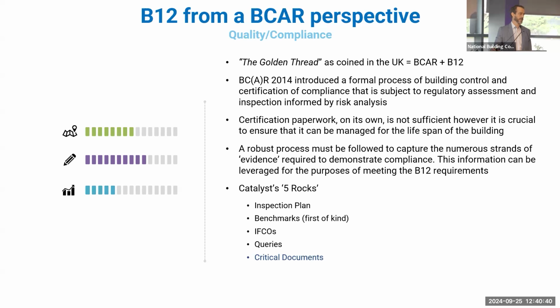Is the lifespan of that building 50 years? Is it 30 years? How long will the sprinkler system last in its current format? Does the pipework need to be replaced after a 30-year or 50-year period? All that information should be included in what's passed through from a B12 perspective. We've done upgrades of projects where you've gone in and looked at the likes of the sprinkler system and it's falling apart, to be honest. You'd wonder would it have operated as intended if it was actually in a fire scenario in basement car parks or high-rise buildings - it does make you ask the question. Anyhow, a robust process needs to be followed to capture the numerous strands and the evidence required to demonstrate compliance.